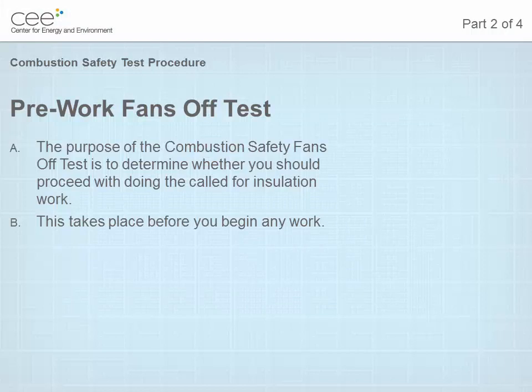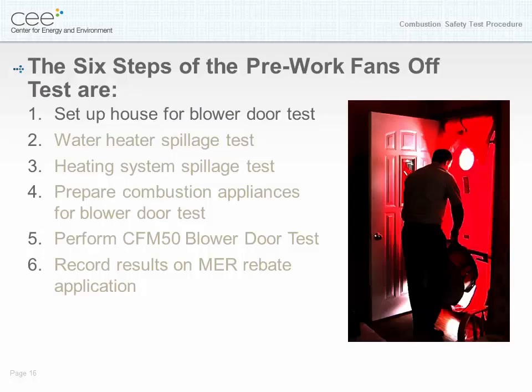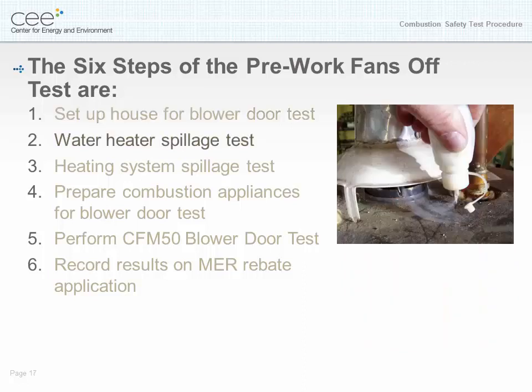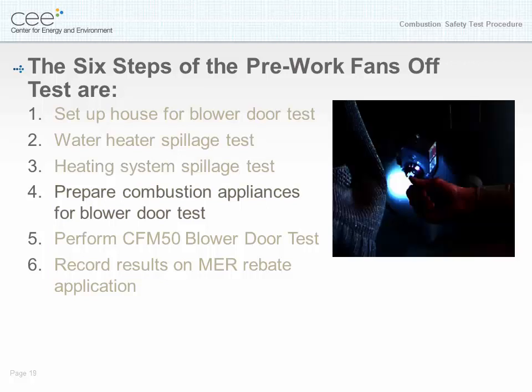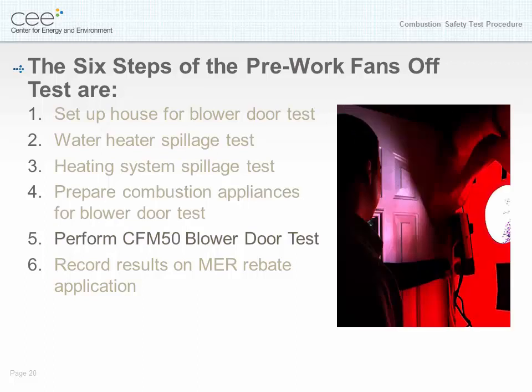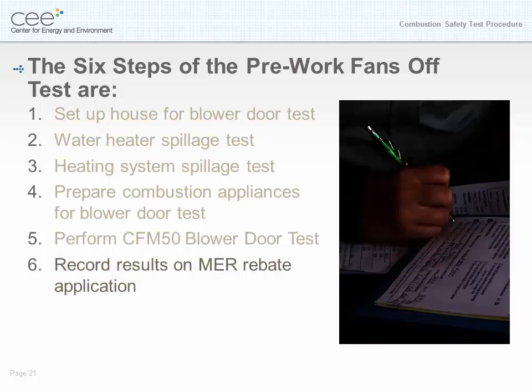Pre-work fans off test. The purpose of the combustion safety fans off test is to determine whether you should proceed with doing the called-for insulation work. This takes place before you begin any work. The six steps are: number one, set up the house for blower door test; number two, the water heater spillage test; number three, the heating system spillage test; number four, prepare combustion appliances for blower door test; number five, perform CFM 50 blower door test; number six, record results on MER rebate application.